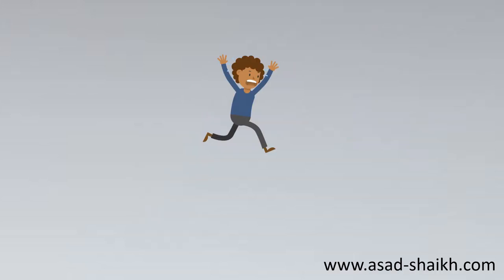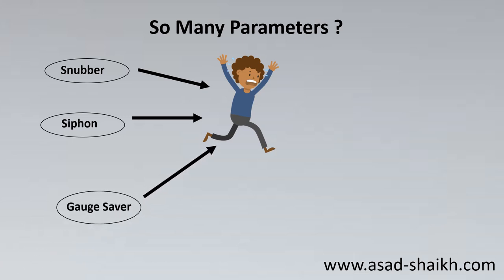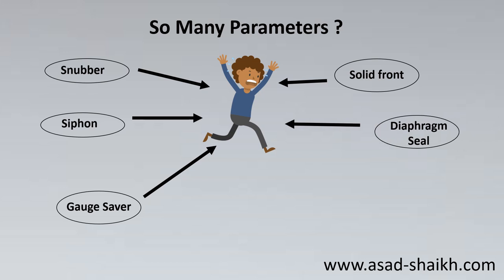When I started with pressure gauges, I realized there are so many parameters to look into. From one side came the snubber, from the other came questions about when to use a siphon — pigtail siphon — and the many different types of siphons available. Then came something called a coiling element, different from a siphon, and then a gauge saver — when to use it, when not to. Then came solid front pressure gauges, diaphragm seals, flushing rings, flushing flanges, and blowout direction. All these details came into picture.